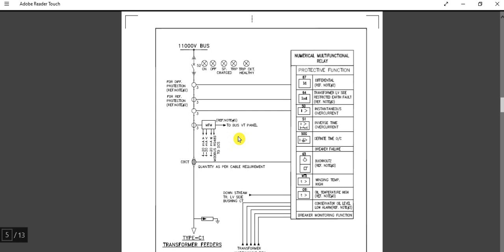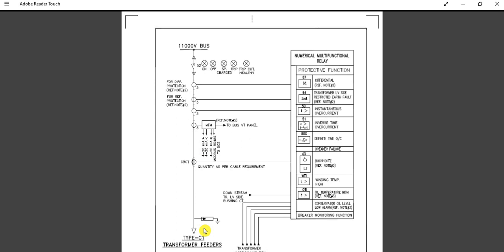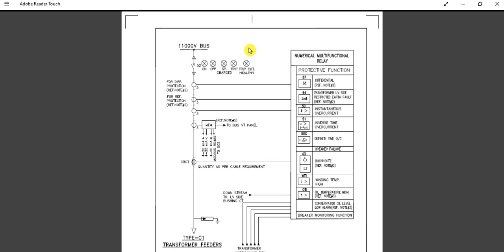In the previous video I discussed the 11kV or 6.6kV incoming feeder single line meter and protection diagram. Today I will discuss the outgoing feeder — specifically the transformer outgoing feeder. From the 11kV or 6.6kV switchboard or switchgear, this outgoing feeder goes to the distribution transformer, for example an 11kV/415V or 6.6kV/415V transformer. Keep in mind: this scheme is applicable for oil-filled transformers only, not for dry-type transformers.